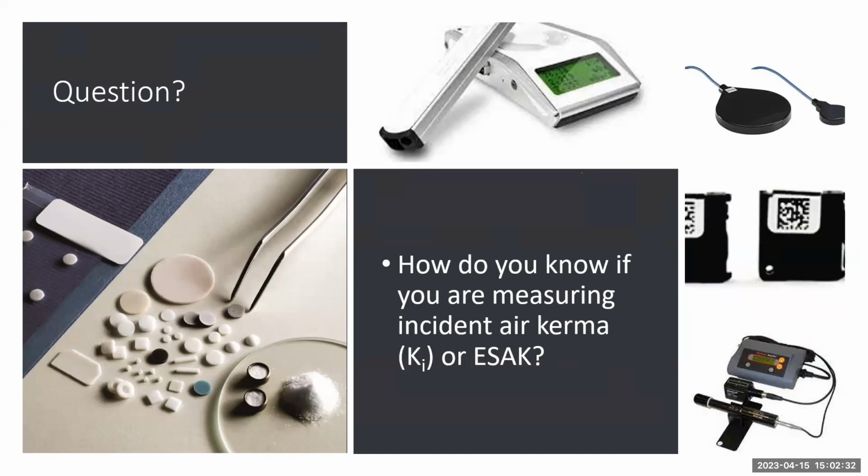Well, the answer lies in what type of detector that you use. Yes, someone, Mohd, has said that if the detector has a lead back, it's incident air kerma. Thank you very much, that's exactly right. It depends on the detector that you're using.